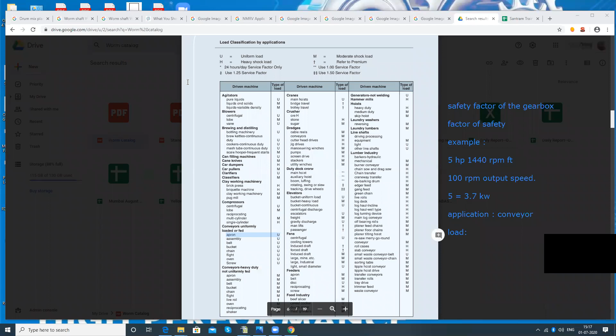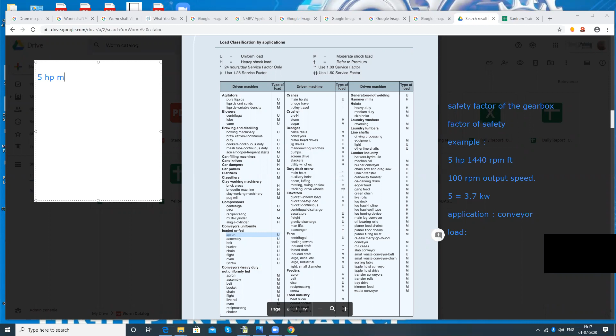So it is a light duty application. In light duty application, the difference between the motor HP and the gearbox capacity will be almost the same. So if it is a 5 HP motor, it means it is a 3.7 kilowatt motor. Okay, and the safety factor will be only 1 because it is light duty. So light duty safety factor is 1. So for our gearbox selection, that is important, the gearbox selected will be the same capacity as the motor, so 3.7 kilowatt.